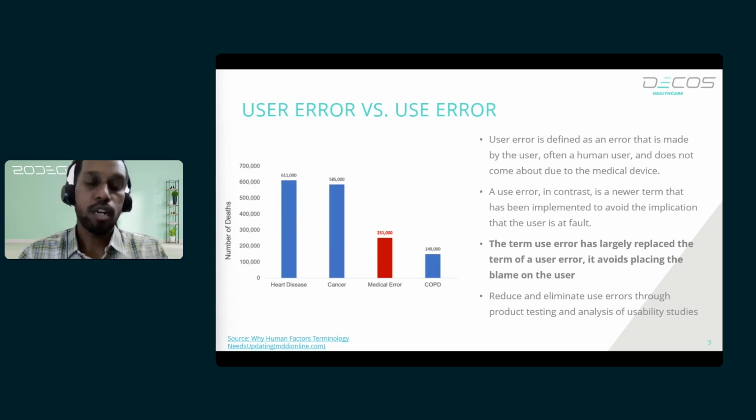Now instead of a mobile phone, take a medical device in its place. Say if you're going to turn off the device and instead of turning off, you are going to restart the device, the entire functionality of the device is going to get restarted. And the person, the user or the patient who is inside the loop of the medical device is also impacted. So the impact of use error can be multiple. It can either be catastrophic or it can be some minimal impact on the user. If this action is done on a medical device, we'll be terming it a use error, and we'll not put the deliberate action on the user.